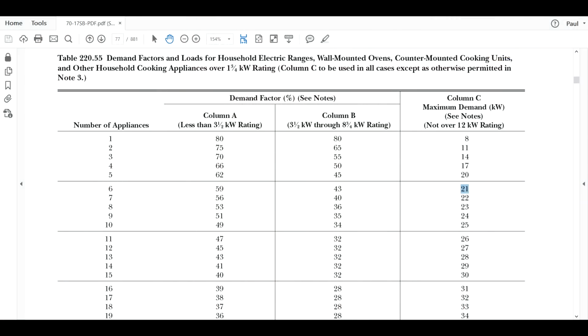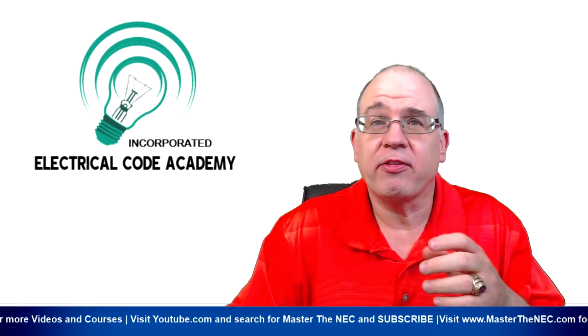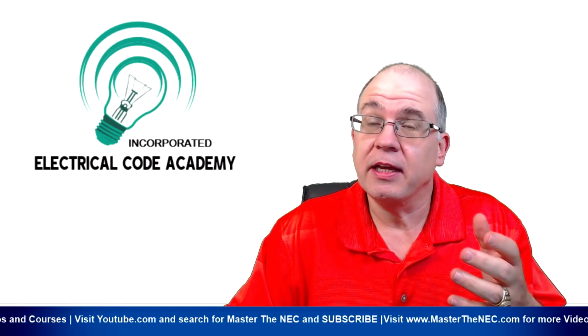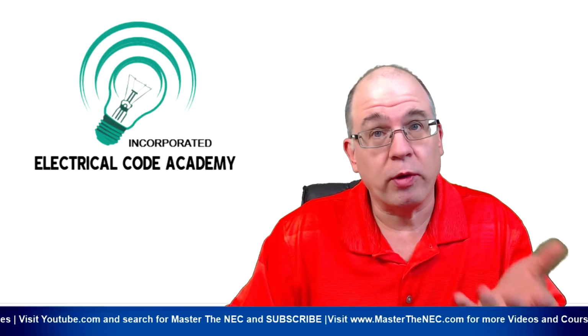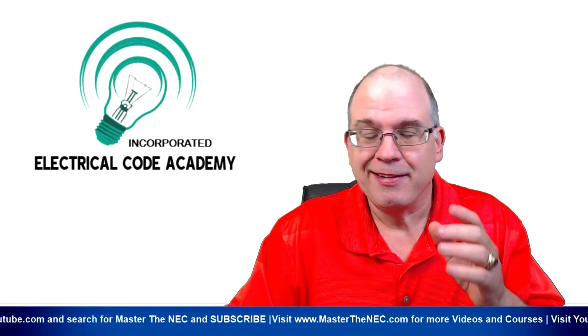So here's the code. I'm going to go back. Okay, I'm back in the code. And we went down to 6 here. There's 6 ranges, and in column B, each range is obviously 8 kW, as we saw. So the value is going to be 43%, and that's going to be our demand factor. And to be honest with you, that might be one of the questions on the exam. It simply wants to know what is the demand factor, and in that case, it would be 43%. It's not what our question is, but that's what you could get.